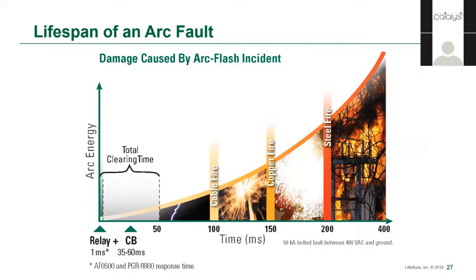As already discussed, the energy release of an arc flash is a function of time — the longer it persists, the more energy is released. As a real-life example, think of holding your finger over a flame versus moving it quickly across. We want to now shift gears from current limiting fuses to another product that can be designed in or retrofitted into existing equipment. I'm referring to arc flash relays. The principal idea of an arc flash relay is to limit the time an arc persists in the event of a fault, and thus minimize the energy released in the system.